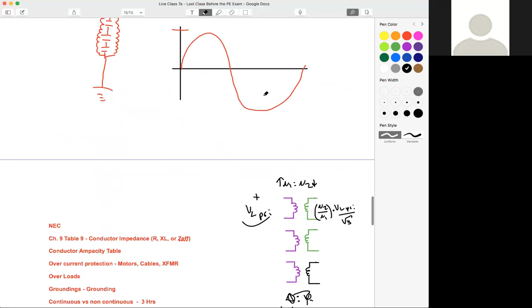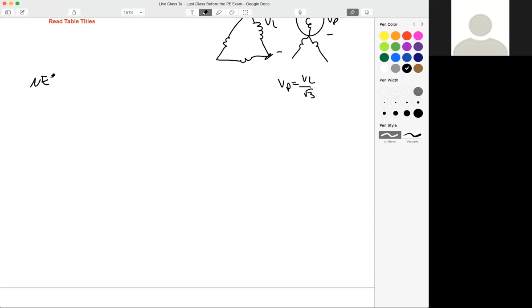Yes, so that's chapter 9, table 9, right? So that's NEC chapter 9, table 9. That table, you've got, ignoring whether we're working in metric or imperial, right? We're either going to be in per kilometers or per feet. Even ignoring that, there's 3 things you're looking at for that table.